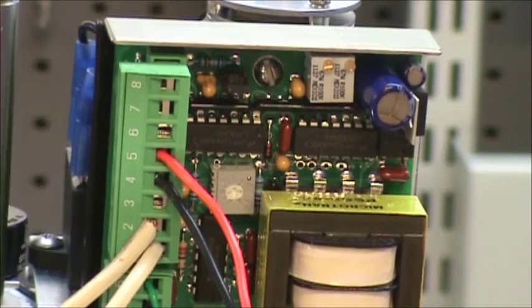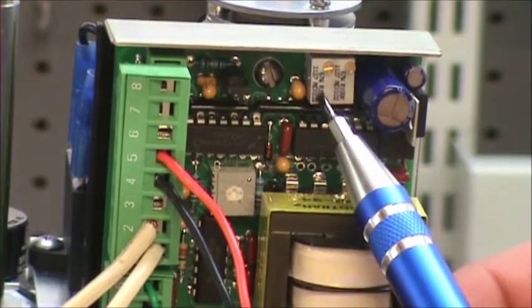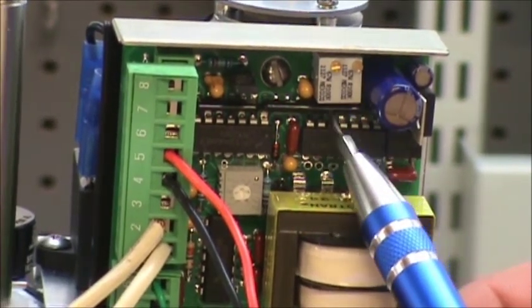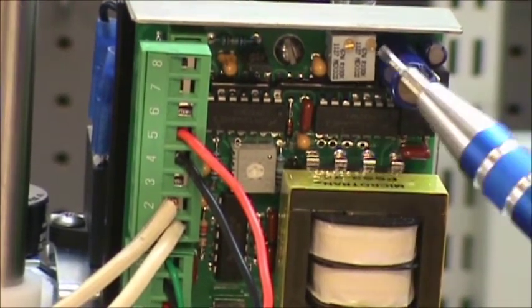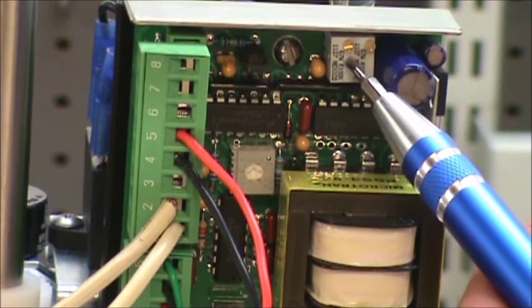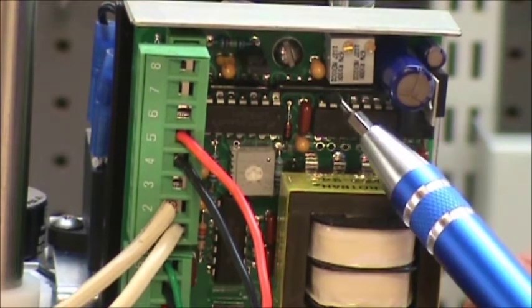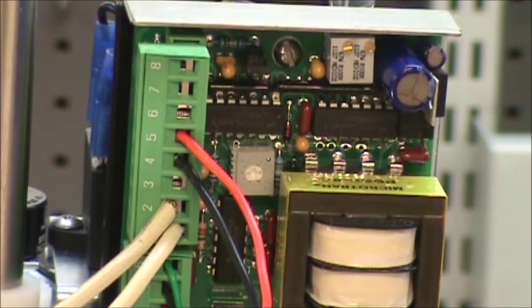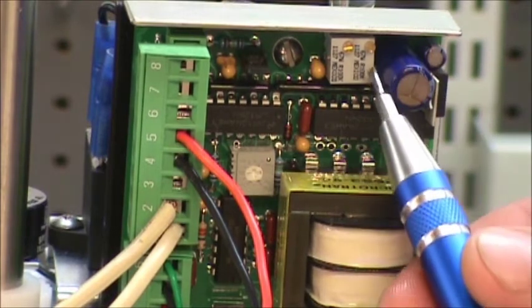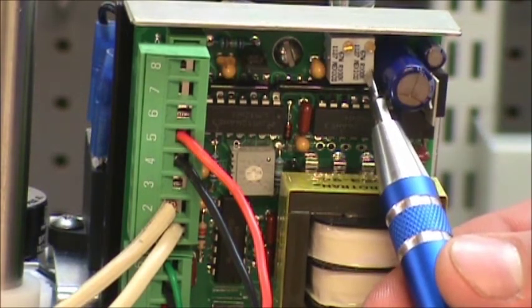So after you've calibrated the zero trim potentiometer here by setting it to 4 milliamps and rotating in small increments clockwise until you've reached the desired position, when you're finished with that, you can move on to the span trim pot, which is here on the right-hand side.